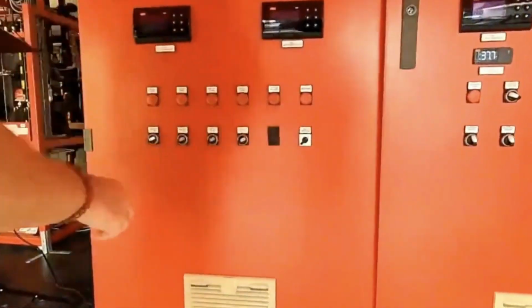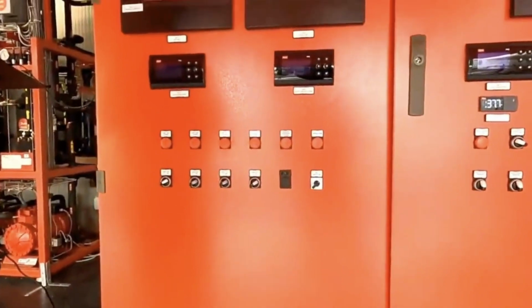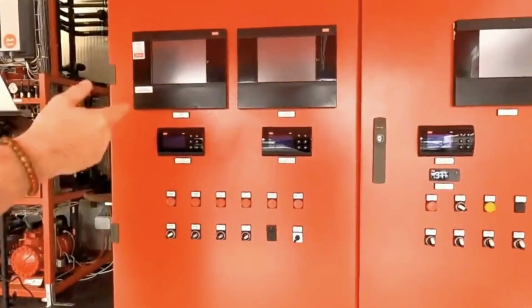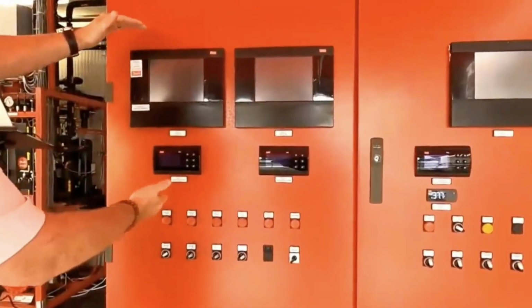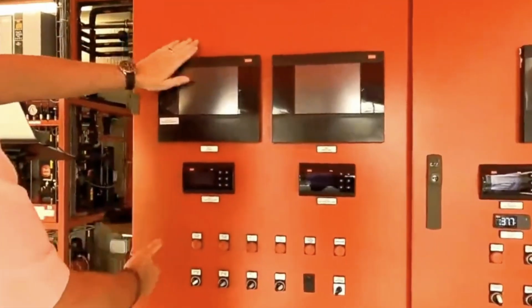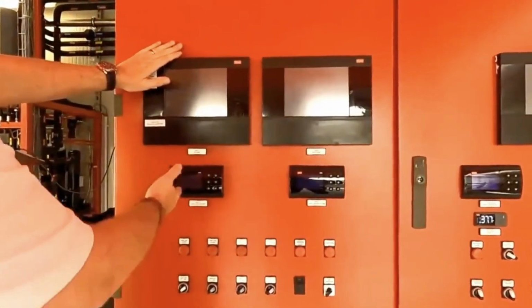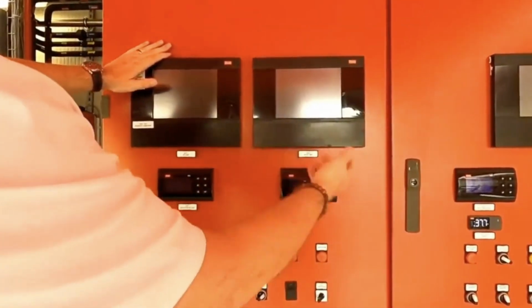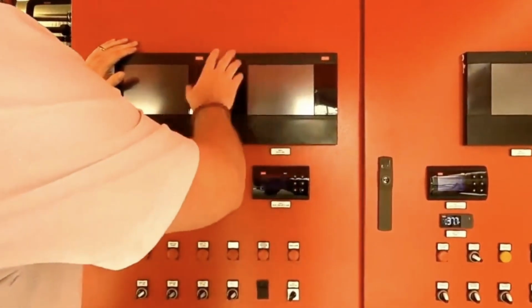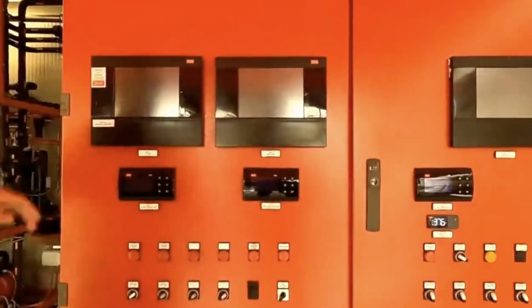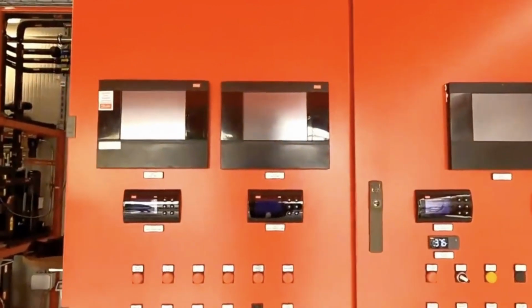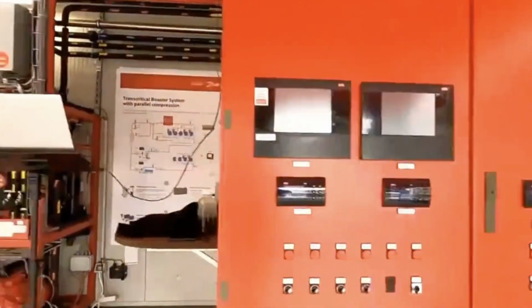I've got the unit currently set to parallel compression with multi-ejectors. Again, as I pointed out earlier, the selector switch will let this system manager 800A power up with the pack controller. If we select 2, this will power down, this will power up, and so on for application 3. So that's our power.